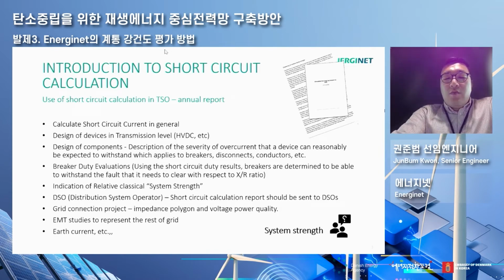Also, breaker duty evaluation uses the short circuit duty result. Breakers are determined to be able to withstand the fault they need to clear with respect to the X and R ratio. For DSOs, which are connected to TSOs, we need to give them indications of relative classical system strength, and the short circuit calculation report should be sent to the DSO. On top of that, the DSO can come up with its own plan, and the grid connection project can be carried out.